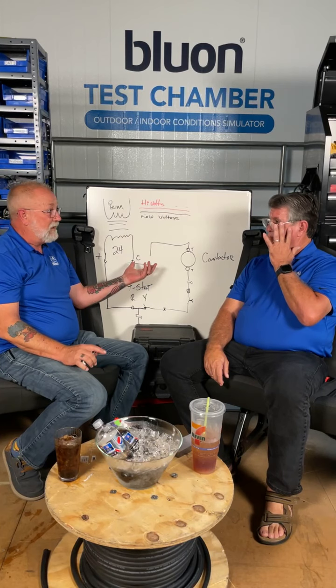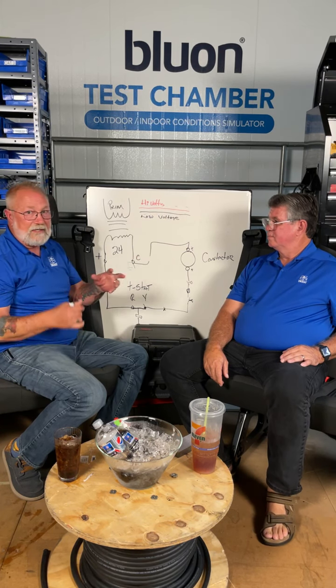So on that, if the thermostat is now calling for cooling, that means this switch is closed. If we have a break on the common, again, you're going to read 24 volts between here and here, but you're not going to read 24 volts between here and here, because the common is broke. How does the common get broke? If it's a split system, again, it could be a rodent issue. It could be the people have got a gardener and somebody hit it with a weed whacker. It could be where they've connected the condensing unit wires to the thermostat wire. I've seen it time and time again where it's actually corroded in the wire nut and gives you a bad connection.